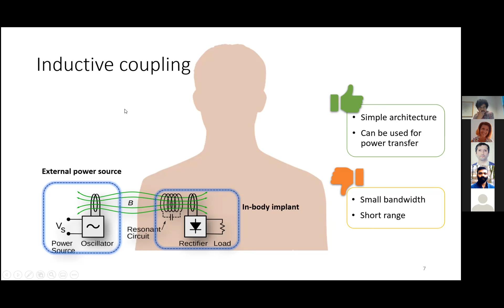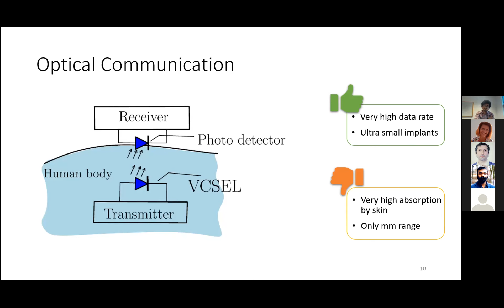Moving on, we can also have ultrasound communication, which uses ultrasound signals for communication, and it has really low attenuation and low power. But the main problem is that if the implant is placed behind the bones, there can be no communication because all the signal is reflected by the bone, and the data rate is also not that high. And then we can also have optical communication, which uses infrared signals. We can have a really high data rate, and the size of the implants can be made really small, but this is not suitable for deep implants. It is only good for superficial implants, like implants placed just under the skin.